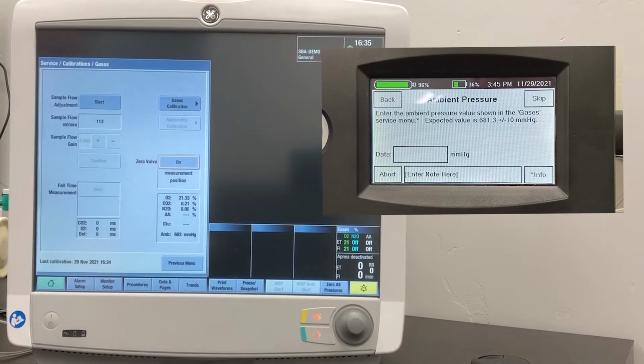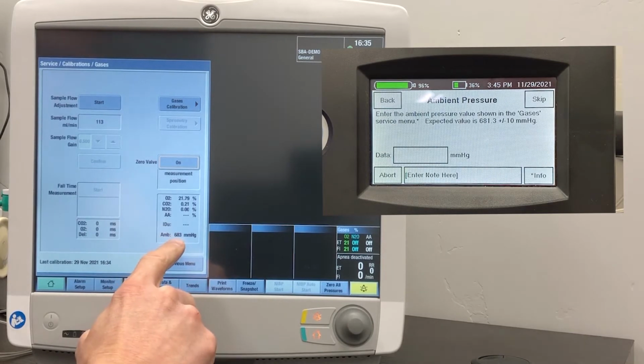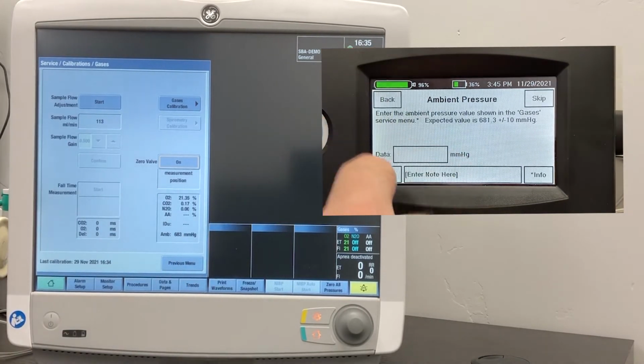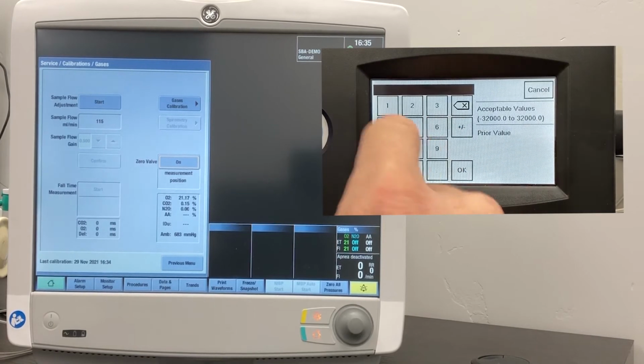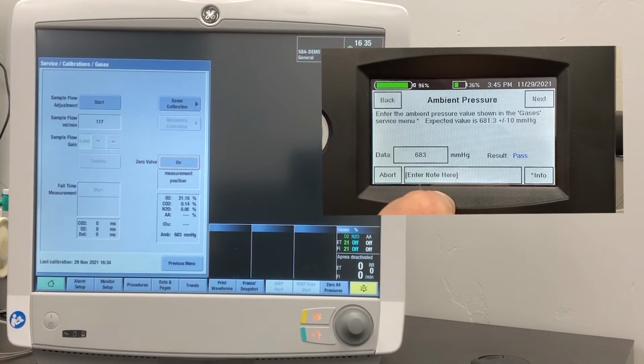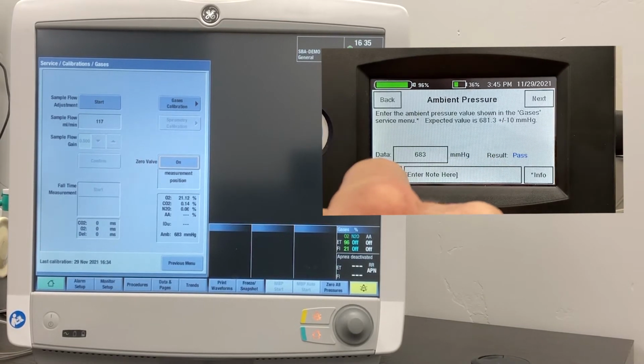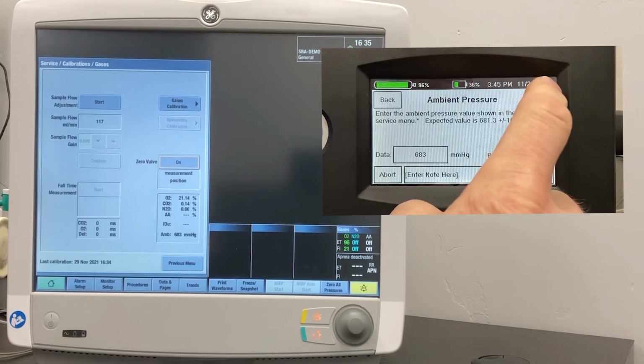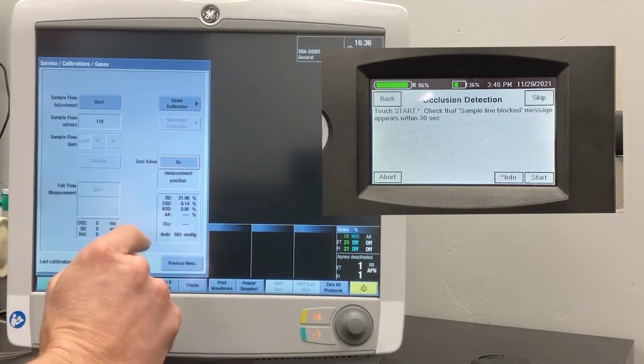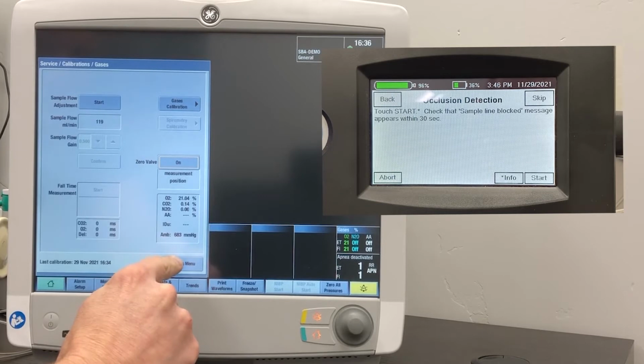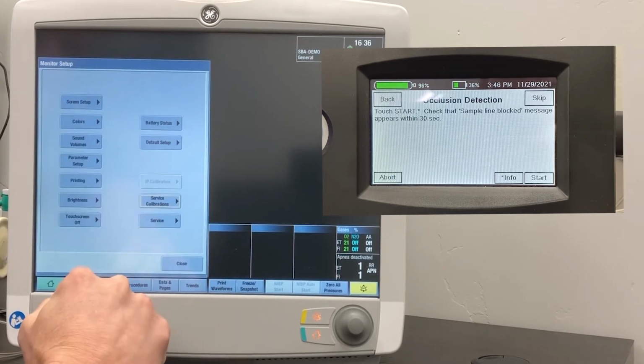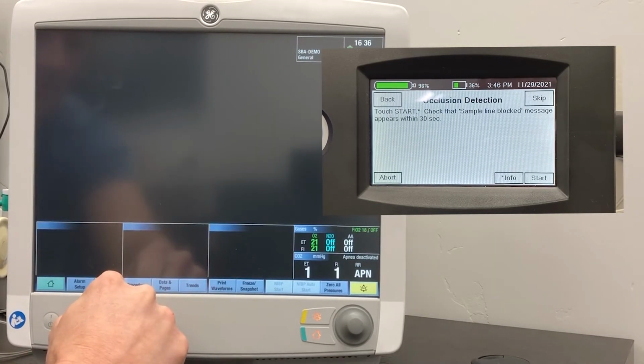Now we're going to look for the ambient pressure, 683. You can see over here the expected value is 681 plus or minus 10, so that's a passing result. We can tell already. So we'll enter 683. You can see that it's passed. Okay, for the occlusion test, we need to exit out of this screen by hitting previous menu twice and then close. Here we are in the normal screen.